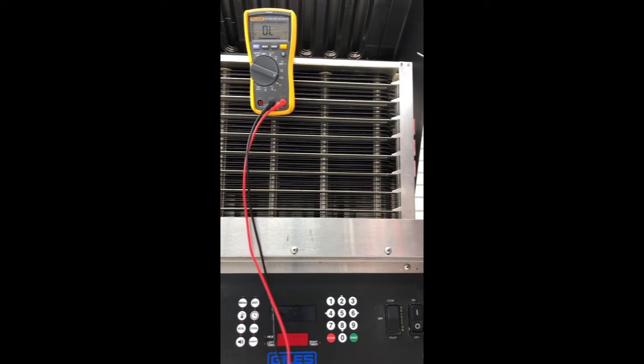A lot of times what causes that is when these filters are cleaned in a fairly aggressive solution, then it'll attack that aluminum and copper. Aluminum and copper aren't always the best of friends, so you'll start to get corrosion in there. You can take some emery cloth or something and try to clean that up and get in between there. A little emery file like you use for your fingernails works extremely well. You can just ease that in between the two and work it back and forth until you get that connection back. It's only going to be temporary. If they don't change the cleaning solution, it's going to come right back.